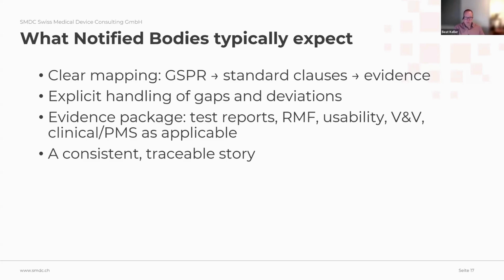And often you say, okay, we fulfill this GSPR requirement by a certain clause of a standard. So you provide a test report of that standard, but don't only provide the test report; also provide where the real fit is. So your risk management file, a usability document, a V&V document, whatever, not only the IEC test report, because often notified bodies don't accept only having this report. They want to see the real content of the evidence.